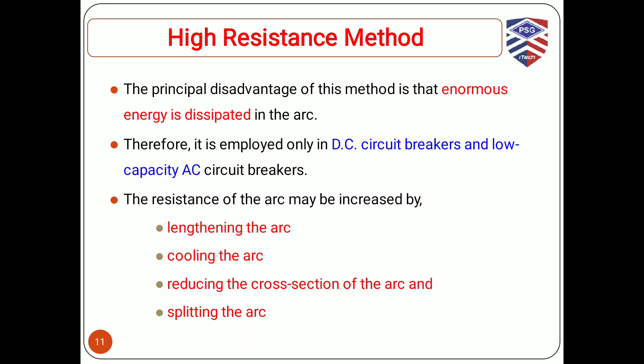Let's see them one by one. First, the lengthening of the arc. The resistance of the arc is directly proportional to its length. By increasing the gap between the circuit breaker contacts, we lengthen the arc. If the length of the arc is more, the resistance of the arc will also be more. We already know that if the resistance of the arc is more, the arc can be interrupted very easily. So by lengthening the arc, we try to quench it.